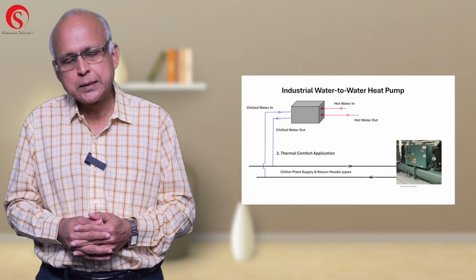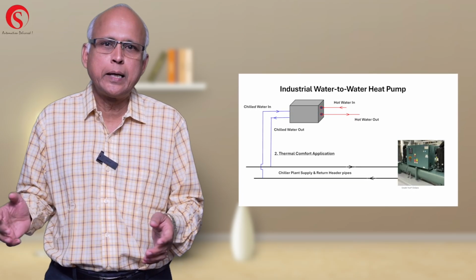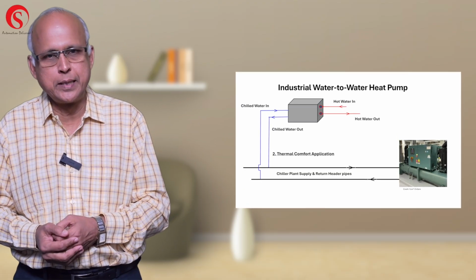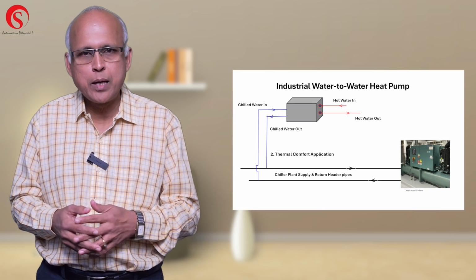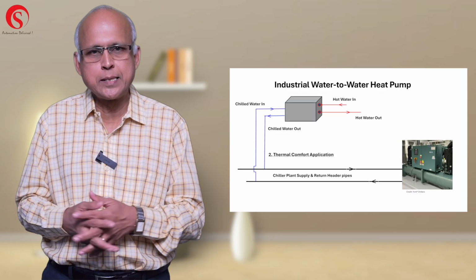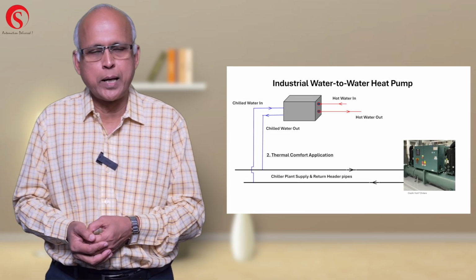Okay, now let me move to the comfort air conditioning requirement of chilled water. Many of the big large industries and factories do have a chiller plant to take care of thermal conditioning, the normal HVAC design. Depending on the requirement and office size, it may be a 50 ton, 100 ton, or 150 ton plant. Many a time I want to narrate one instance where the client has a chiller plant. He said, give me a water to water heat pump. Looking at the product catalog and talking to the OEM, he bought the water to water heat pump and installed it. One thing both of them missed was that during winter time, the chiller plant is as good as shut, right?